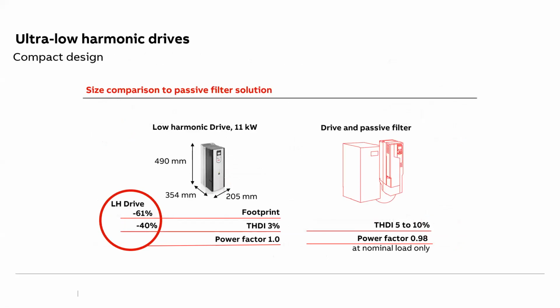Then in terms of size, it saves a lot of space. Most of the time we are working in the real estate sector, where space is cost. So if it helps in saving space, that's a direct saving of money. Normally these filters are very bulky, very heavy, and they occupy a lot of space. With the ultra low harmonic drive, we can completely eliminate this additional filter cabinet. So the size reduces drastically. This is an important feature. The footprint reduces drastically.